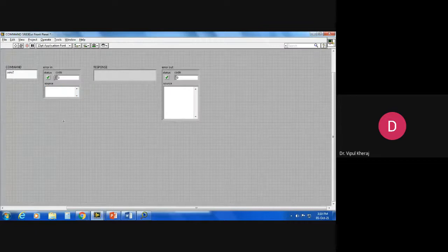Now let us see, if we ask the sensitivity, the response is 25. There are 26 different values that I can set, right? Currently it is set on 25. Suppose I want to change it to 23. All I have to do is remove the question mark and make it 23. Currently it is 25, I am changing it to 23. Basically I am changing the sensitivity. It will be converted into some milliampere per volt or something like that.